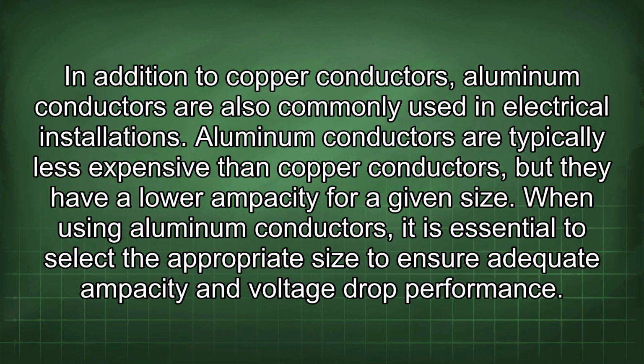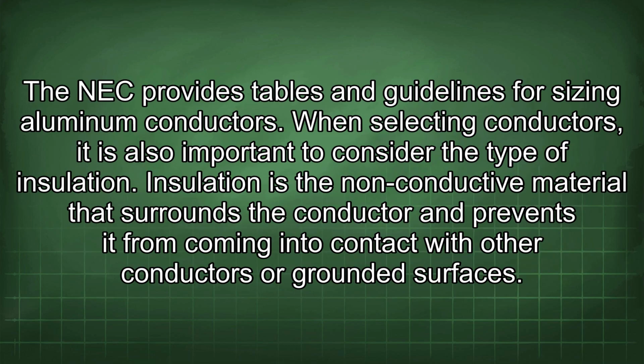In addition to copper conductors, aluminum conductors are also commonly used in electrical installations. Aluminum conductors are typically less expensive than copper conductors, but they have a lower ampacity for a given size. When using aluminum conductors, it is essential to select the appropriate size to ensure adequate ampacity and voltage drop performance. The NEC provides tables and guidelines for sizing aluminum conductors.